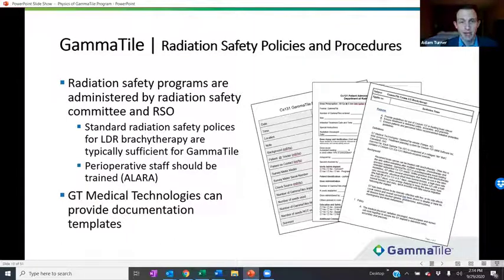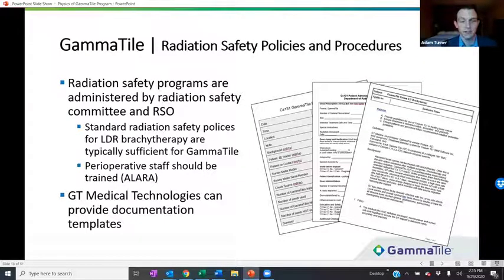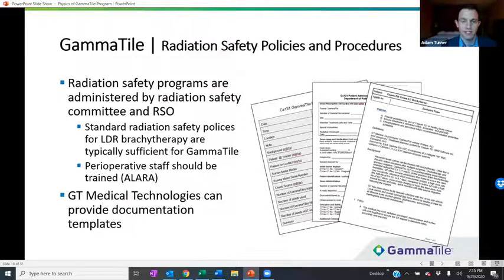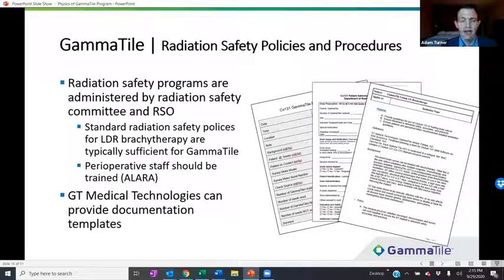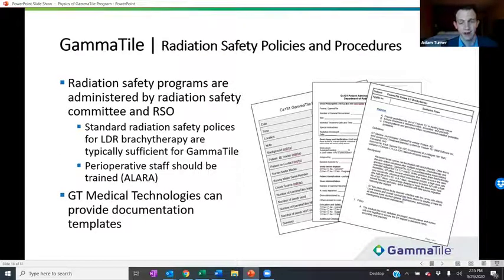Regarding radiation safety policies and procedures, radiation safety programs are fully administered by local radiation safety committees and the radiation safety officers. Your standard radiation safety policies for LDR procedures — like prostate seed implants or eye plaque procedures — are typically sufficient for Gamma Tile. We also always recommend that perioperative staff — the OR staff and ICU staff — are trained in principles of ALARA, time-distance-shielding, and standard radiation safety principles. We have plenty of templates, including a full policies and procedures generic template that can be modified for your individual institution.